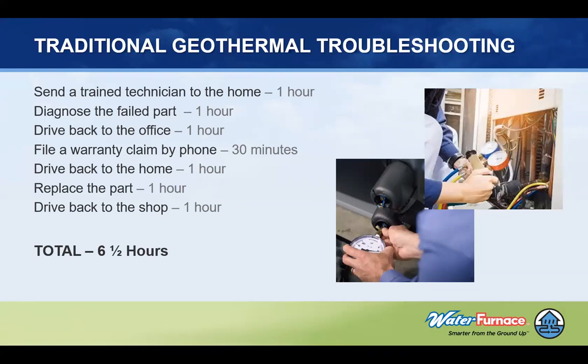As we do an assessment, and this is meant to be kind of the minimum that it would take to service a piece of equipment, servicing a traditional geothermal by troubleshooting that manual way, we have to send a technician to the home. We diagnose what the failed part is. That typically would take an hour at least. Drive back to the office, file a warranty claim by phone, then drive back out to the home, replace the part, and then drive back to the shop. If you do that, it takes about 6 hours of time to just do that troubleshooting to identify the part and get the right part for replacement on a warranty repair.